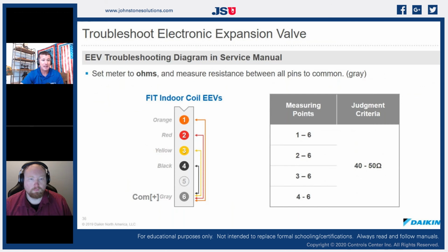Our electronic expansion valve, it's really this simple. It has 4 windings in it, all referencing back to ground. It's running on 24 volts AC. That's why we're using that separate transformer. If we're going to open an expansion valve, we're just going to fire it 4321, 4321, 4321 until we open it up. When we close it back down, 1234, 1234, 1234. So we can check the resistance on those windings to make sure that they are good. So with our Daikin EEVs, we're simply going to unplug our plug.